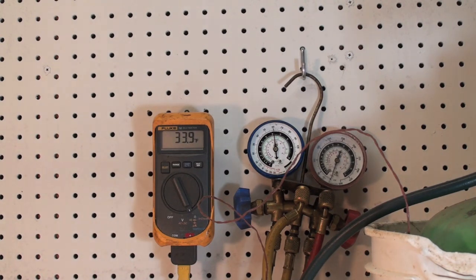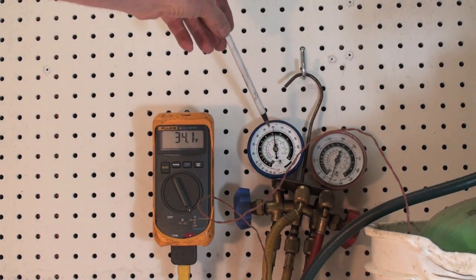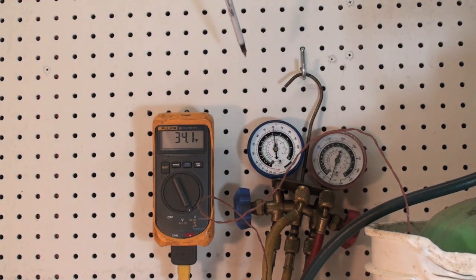So we have a temperature gauge on that pressure gauge. That is a temperature gauge. We make a lot of thermometers that read temperatures just that way. Many thermometers are saturated mixes of some kind of refrigerant, and the gauge itself is really just a pressure gauge.